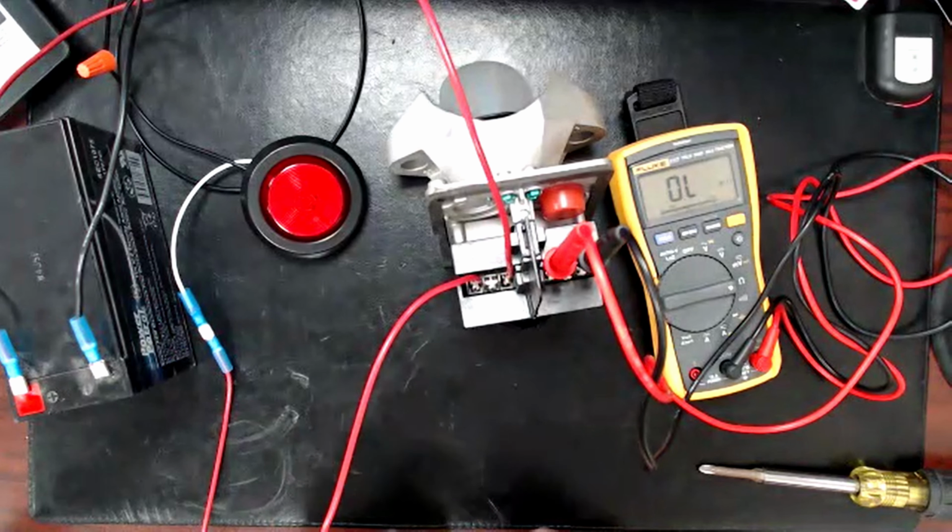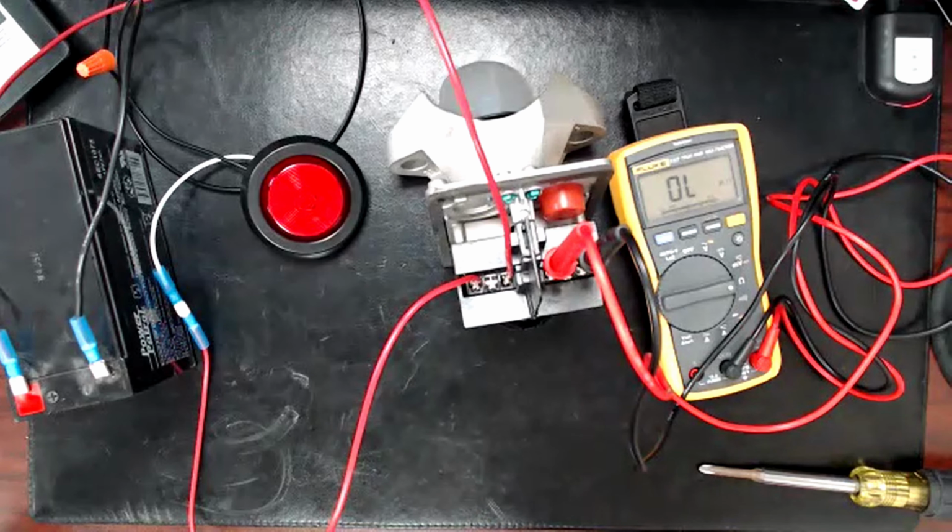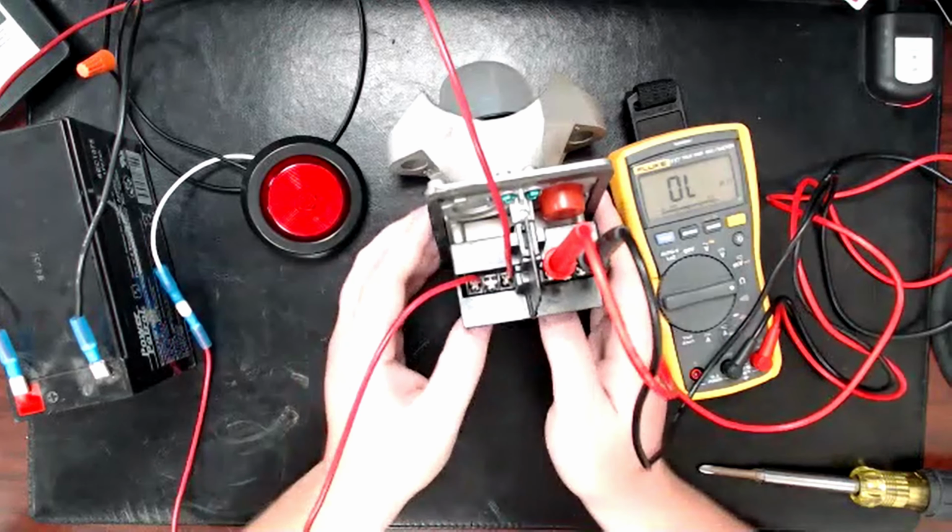Also, Gamewell panels, as smart and wonderful as they are, they don't have the programmable NAC circuits, but they do have auxiliary power. So you can wire this up with Gamewell panels, Notifier, Fire-Lite, any other brand out there. So if we're doing a lease space and we have to add a sprinkler bell somewhere, or we're doing a school that has an existing system of whatever brand, and they're adding a sprinkler system in the school, and so we have to add a sprinkler bell.